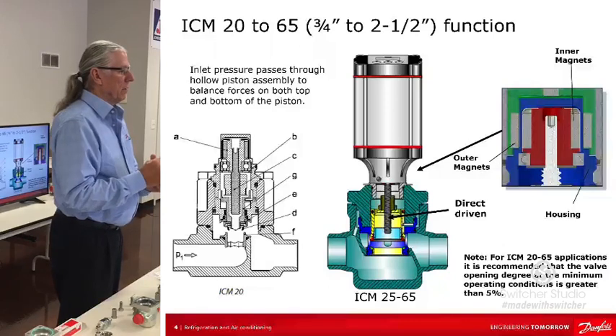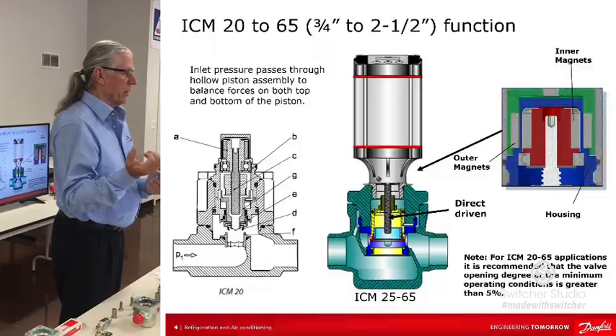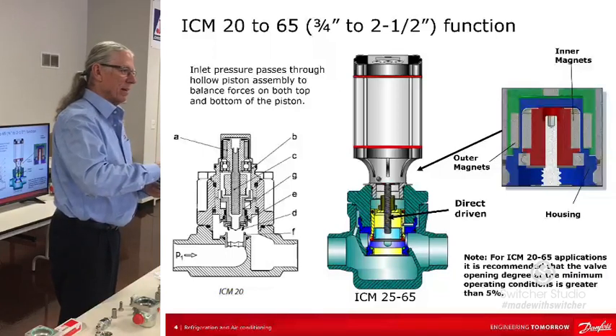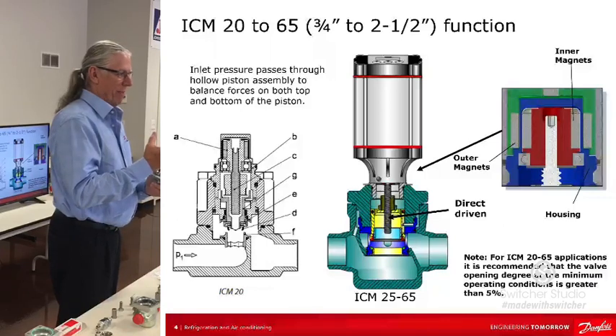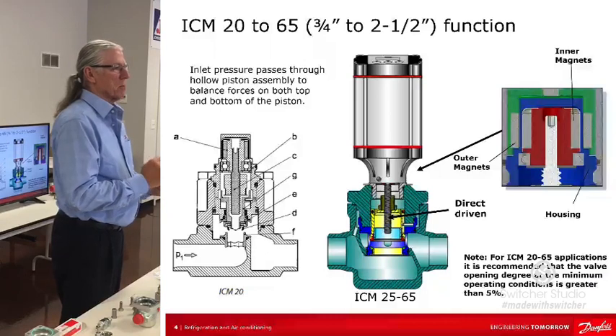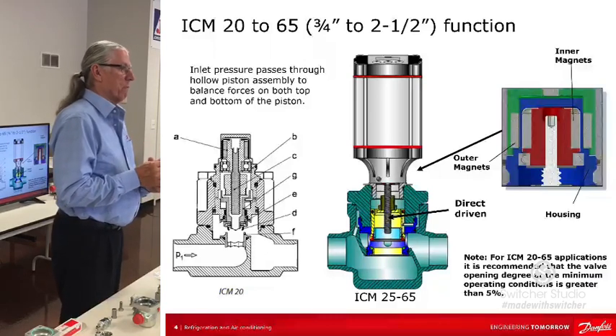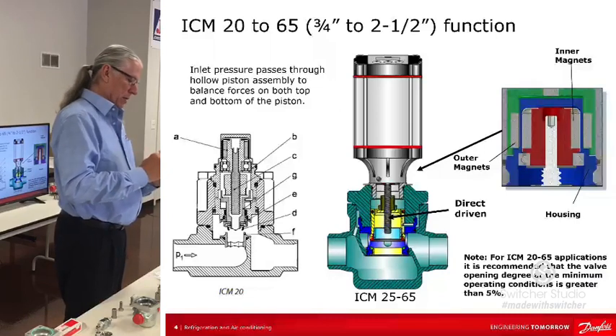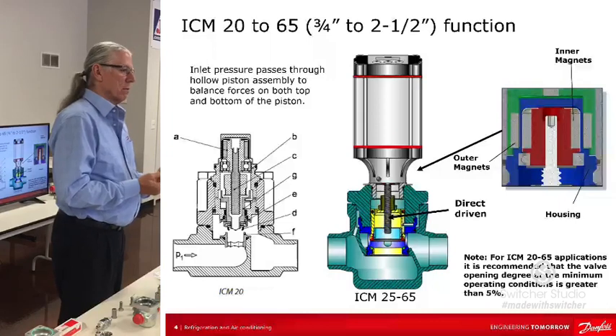An example is, let's say you're working with it and you are taking the actuator off and then you operate this. The encoder is actually not going to help you with that, but it is going to calibrate, and that's how it gets synced back up. So you can go around the encoder if you put an effort into it, but the idea of the encoder is, if you have a blockage in the valve, it always knows where the valve is.